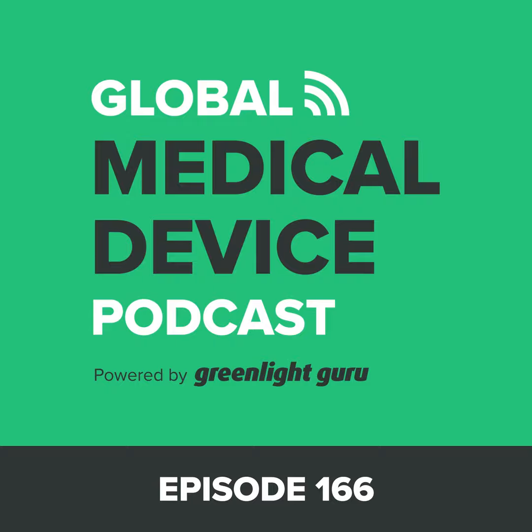And I realized that we had omitted or forgotten, or something had fallen through the cracks, on a particular biocompatibility test. And that's not something you want to forget about, especially if you're about to submit a 510K to the FDA. That's certainly going to be a question, if not a reason for rejection from FDA.